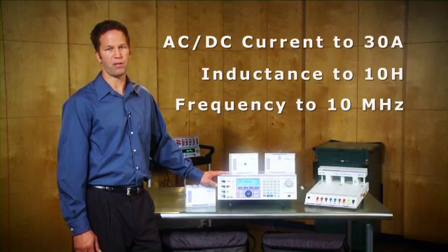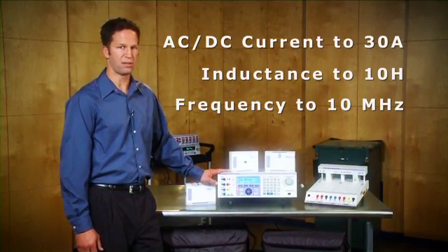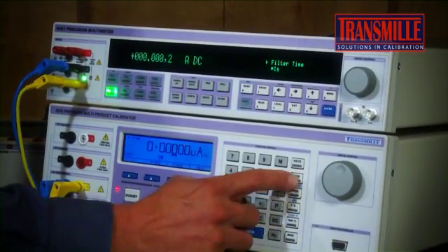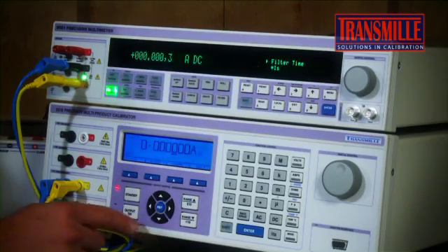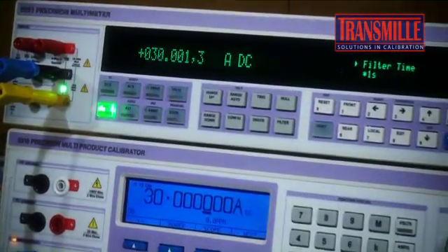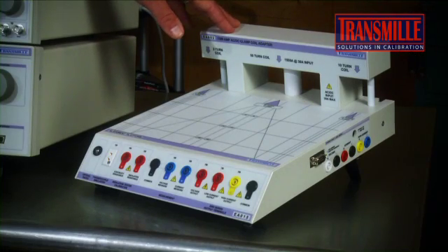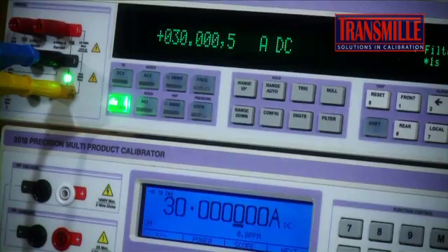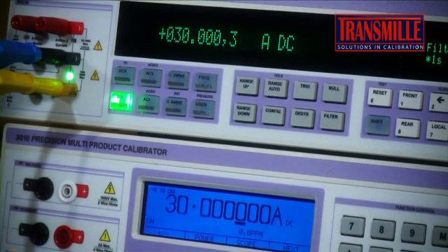Where things really start to differentiate is when we consider AC and DC current. As a standard, Transmille calibrators can provide up to 30 amps AC or DC current output. As a consequence, using our 50-turn coil adapter, we're able to calibrate current clamp meters up to 1,500 amps, while most competitive models will max out around 1,000 amps.